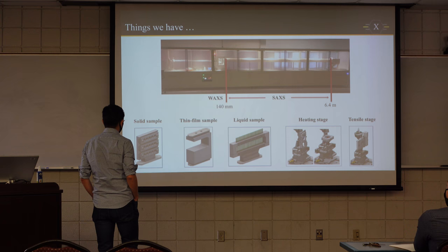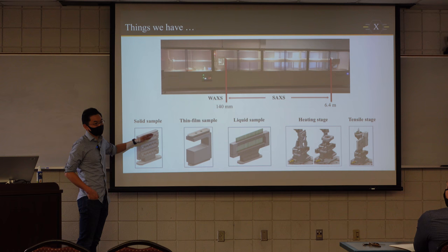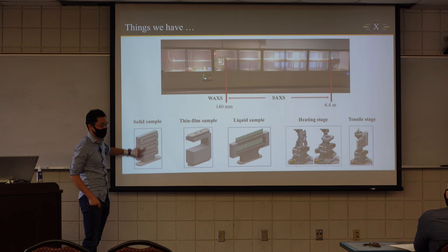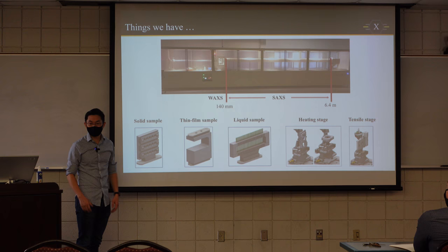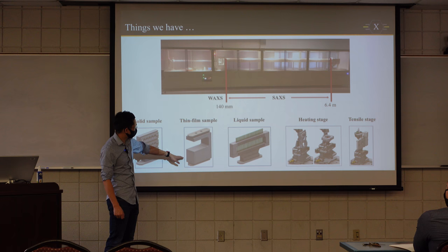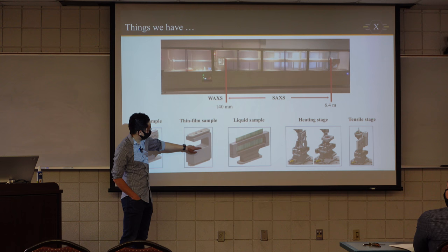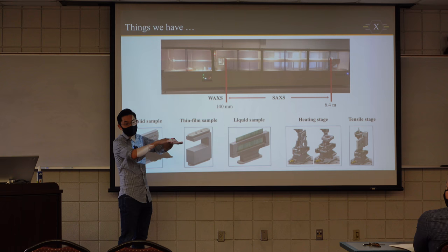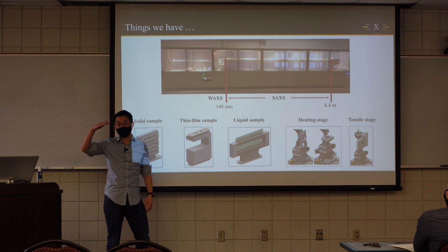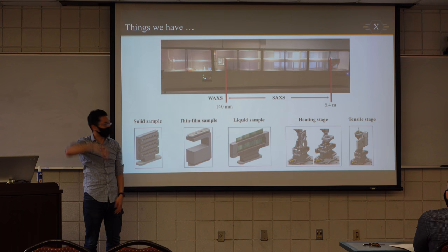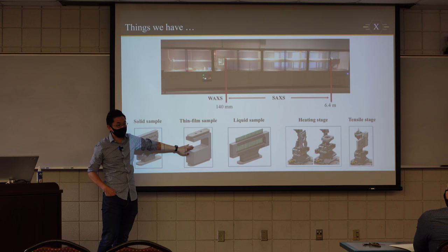Okay? So what are you going to do typically for these? Load the solid samples in there, sandwiched in between. You can mount as many as about 15 samples, and you can measure one by one, or you can program it to measure by itself after you set up the computer program. A thin film sample has a slightly weird geometry. Once you put the film here, you can lie it flat, so when the X-ray comes in, it's shooting at a grazing incident angle. You don't need to mount the top part. The reason they made it cut away is you can mount the sample here or here, so you can shoot grazing incidence from the bottom, or from the top if you glue the sample to the top part. But almost every time we mount at the bottom and just leave it flat there.